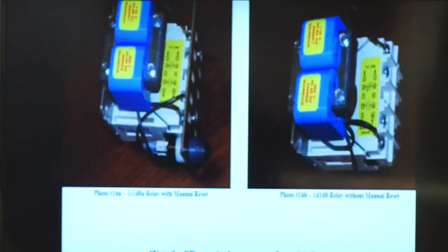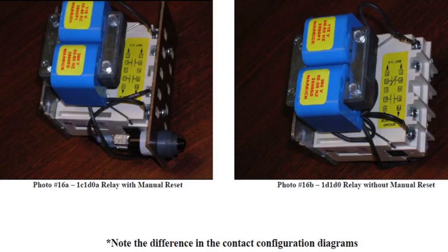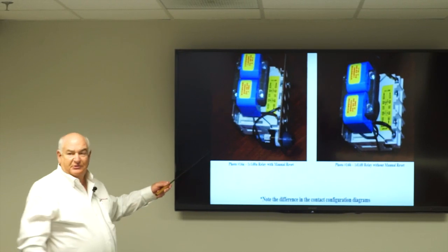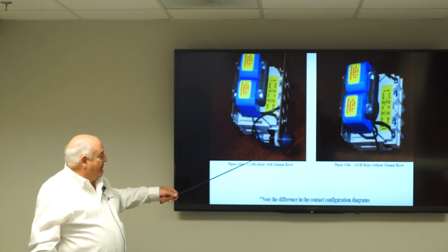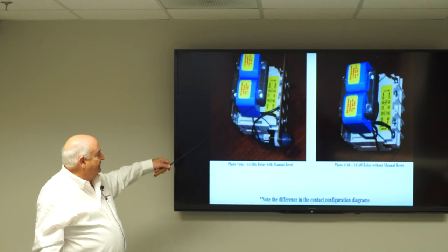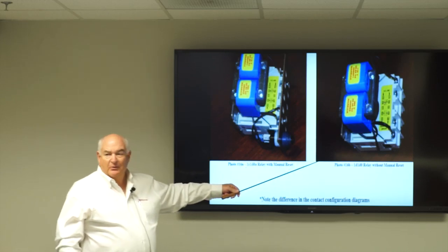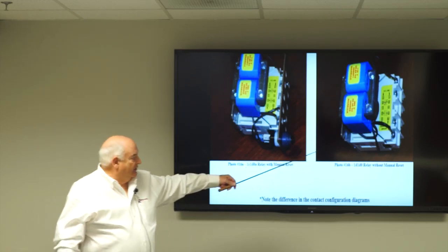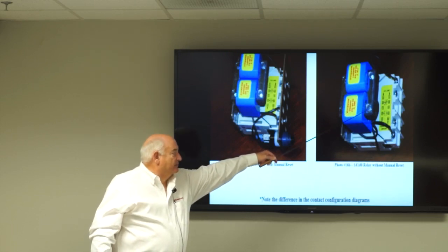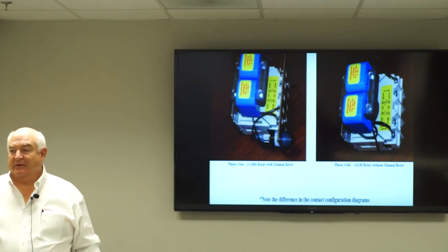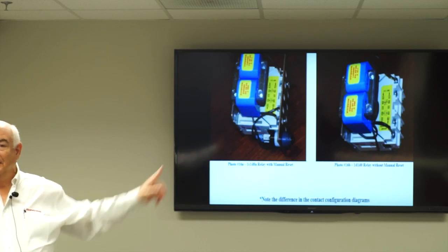What about the second one — the probe type? On the side of the boiler there's a little electrical box with a relay and a manual reset button. If it trips, you push the button and it starts again. What's supposed to be in the cabinet: a manual reset button and a couple of normally open contacts. What was actually installed: no reset button, and a normally closed contact. Low water cutoff number two was inoperative — it was wrong. All done by the owner.